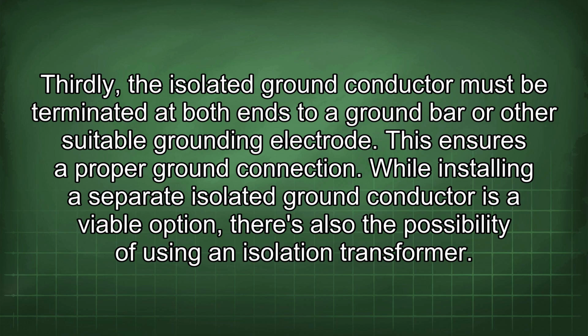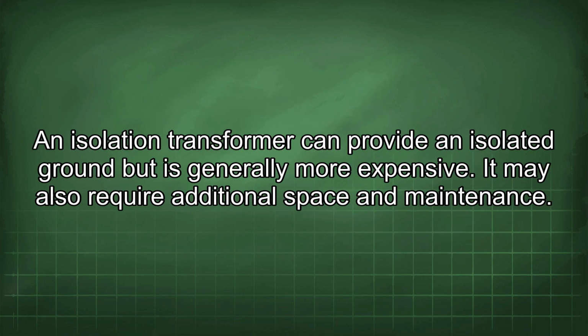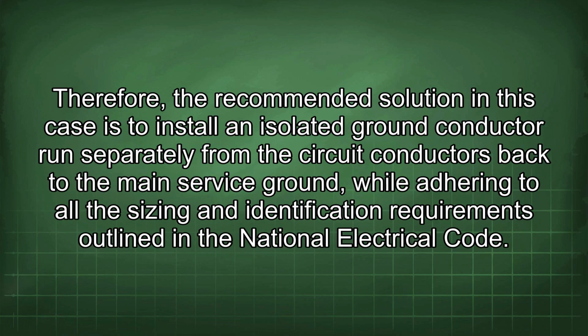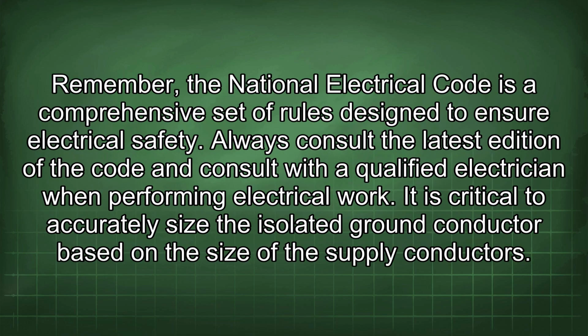While installing a separate isolated ground conductor is a viable option, there's also the possibility of using an isolation transformer. An isolation transformer can provide an isolated ground but is generally more expensive. It may also require additional space and maintenance. Therefore, the recommended solution in this case is to install an isolated ground conductor run separately from the circuit conductors back to the main service ground, while adhering to all the sizing and identification requirements outlined in the National Electrical Code. Remember, the National Electrical Code is a comprehensive set of rules designed to ensure electrical safety. Always consult the latest edition of the code and consult with a qualified electrician when performing electrical work.